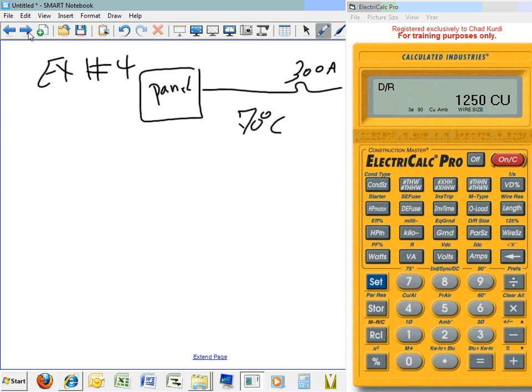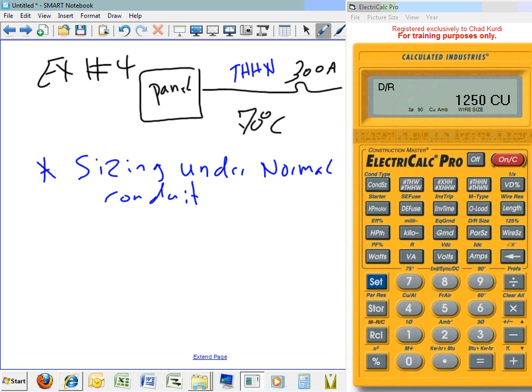Okay, 70 degrees Celsius. My conductors are THHN. And my question for you, temperature, and I need to size the conductor under these circumstances. It's already a panel. Now, it's already calculated the continuous load, so don't sweat it too hard. So the first thing I would do under these circumstances, make sure you go size the feeder under normal conditions. What's the normal condition? Forget the idea that there's a temperature difference. So I'm going to say sizing under normal condition. How do you do that? Condition, not conduit.